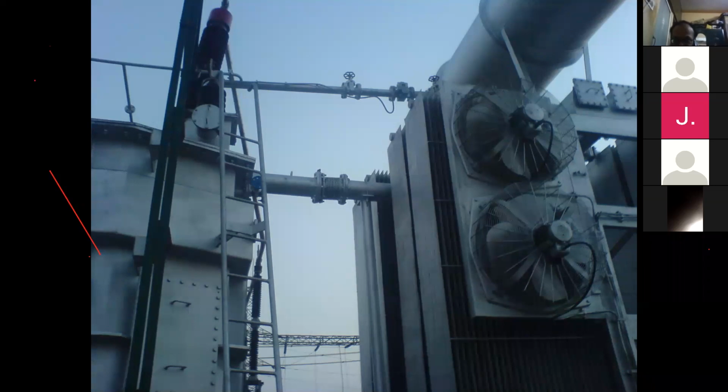And by nature, since an air bubble or any gas bubble is lighter than oil, it moves up to the topmost part, to the conservator tank. In the path we have the Buchholz relay. Therefore, it will capture the gas and it will trip. Hence, it is called a gas actuated relay.